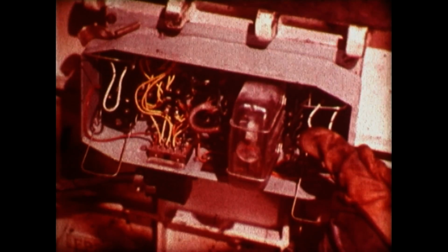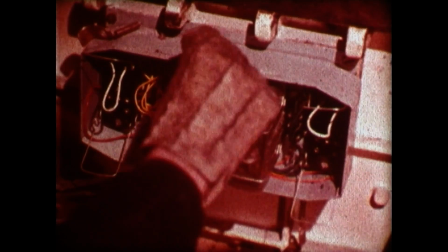Inside the switch, the earth leakage relay and the proving relay had both been removed and were found lying on the floor. And in the open sockets of both these relays, someone had put in pieces of wire so as to remake the circuits. And the stop switch contact had also been bridged with a piece of VIR.